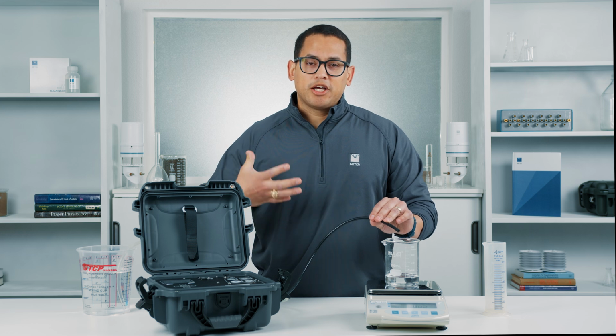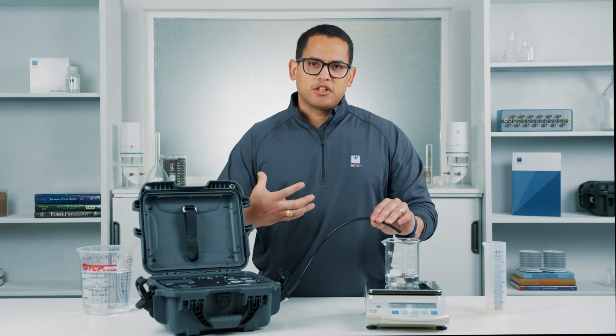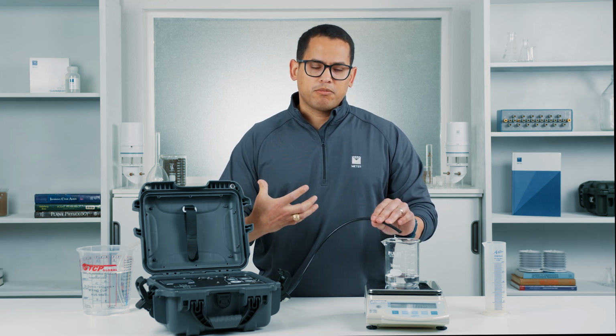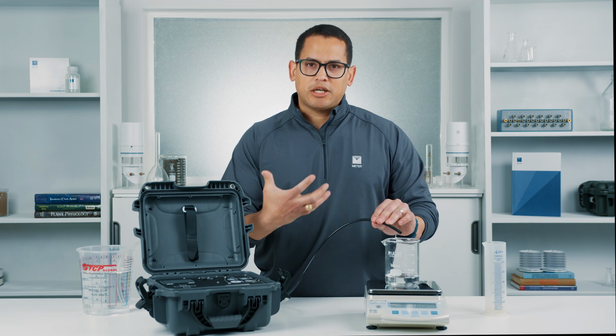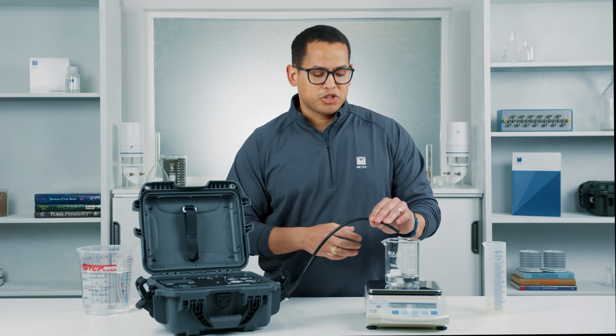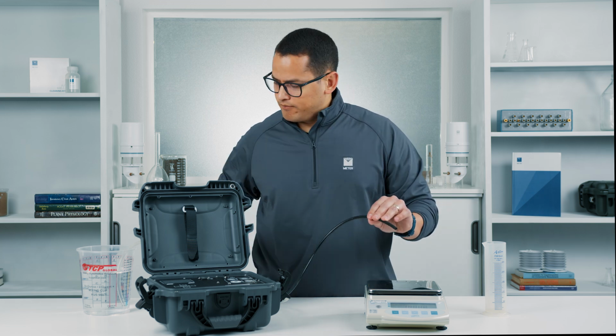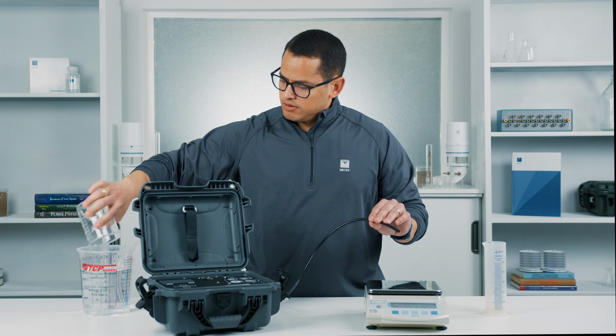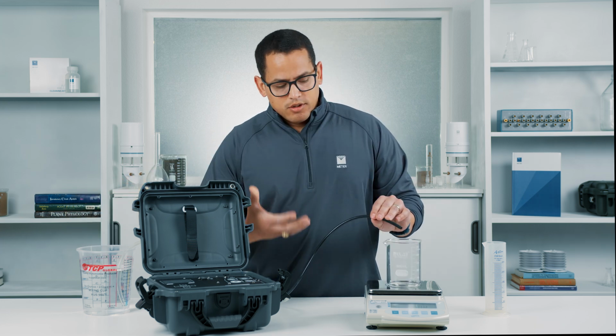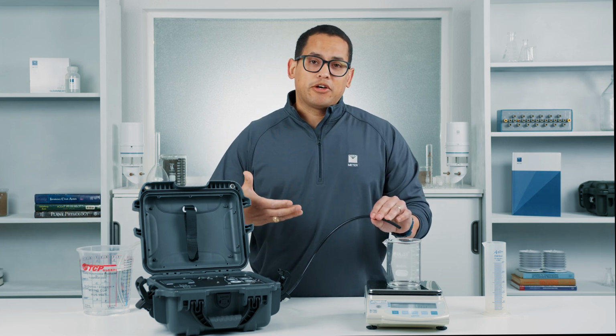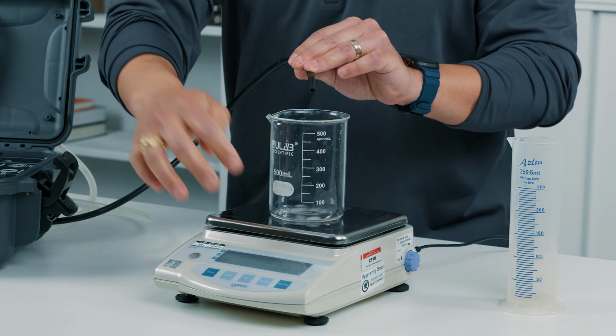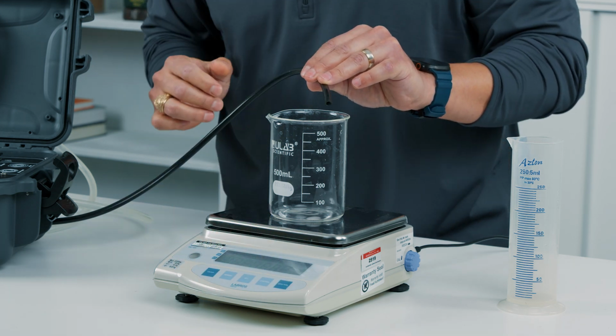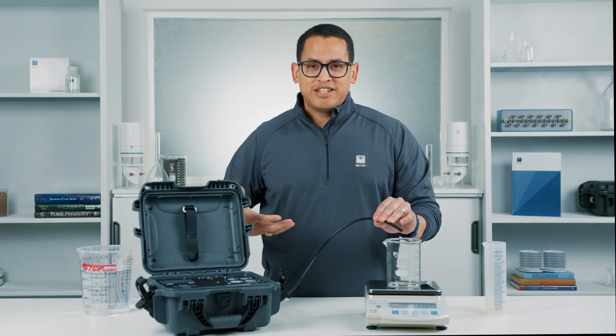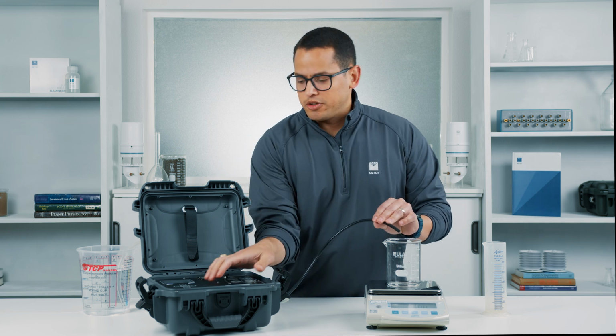Now that we have the line purged and clean, and I feel like it's free of air and just water being pumped through, I'm going to go ahead and empty the container that's capturing the water. That way we can get that calibration process started. I'm going to tare the scale out again just to make sure we have a fresh measurement. Now that we have everything ready, I'm going to hit yes and get the calibration routine started.